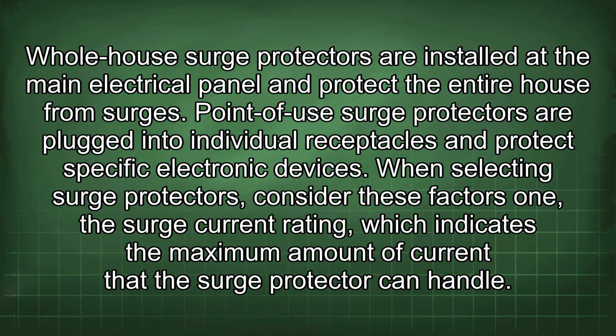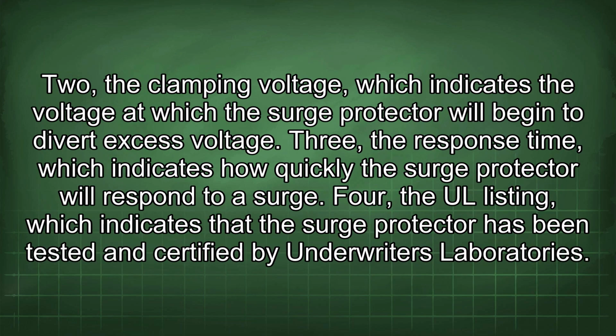When selecting surge protectors, consider these factors. 1. The surge current rating, which indicates the maximum amount of current that the surge protector can handle. 2. The clamping voltage, which indicates the voltage at which the surge protector will begin to divert excess voltage. 3. The response time, which indicates how quickly the surge protector will respond to a surge. 4. The UL listing, which indicates that the surge protector has been tested and certified by Underwriters Laboratories.